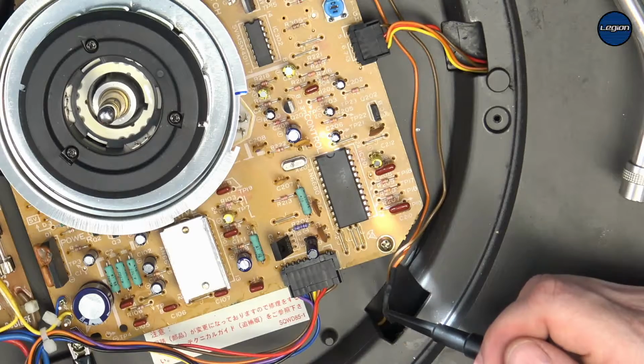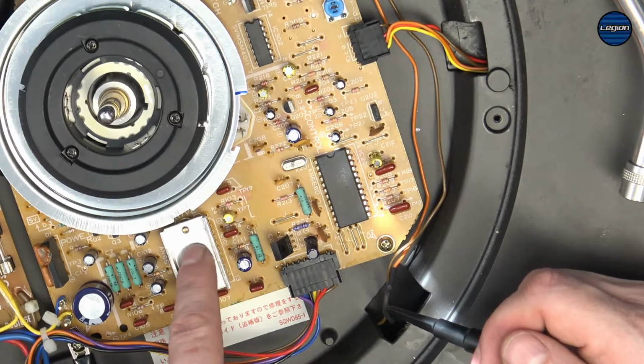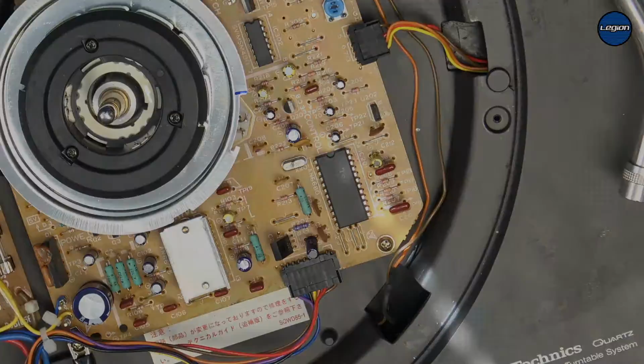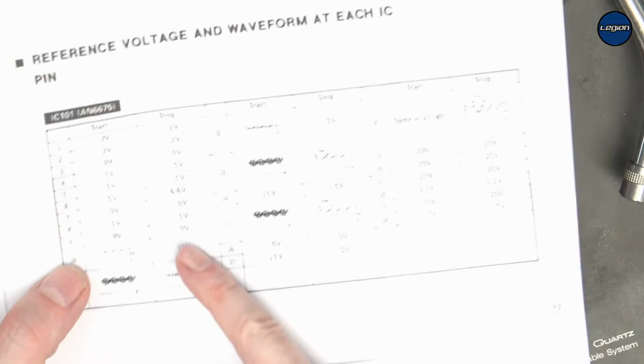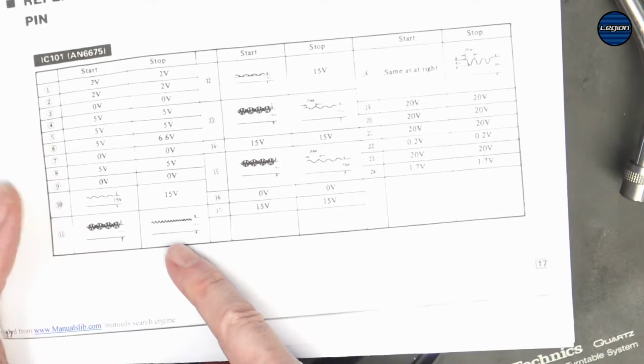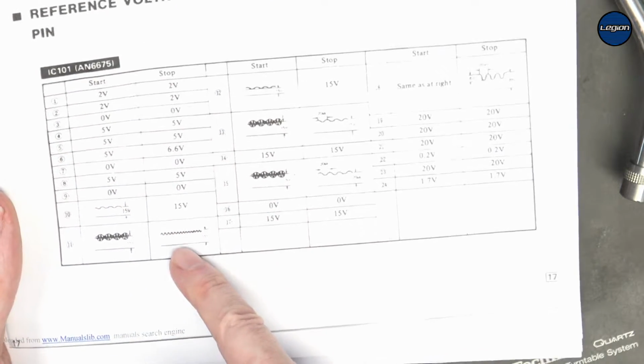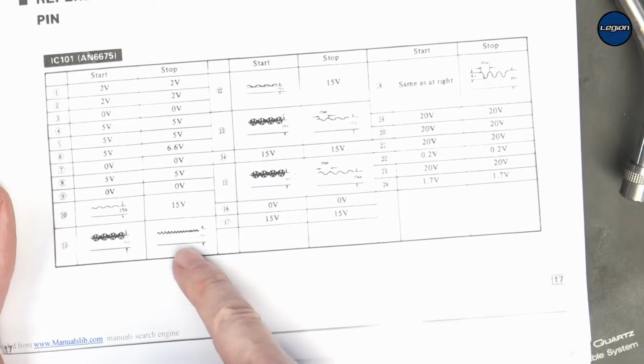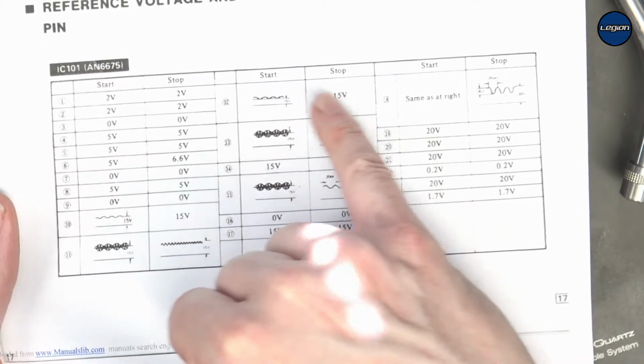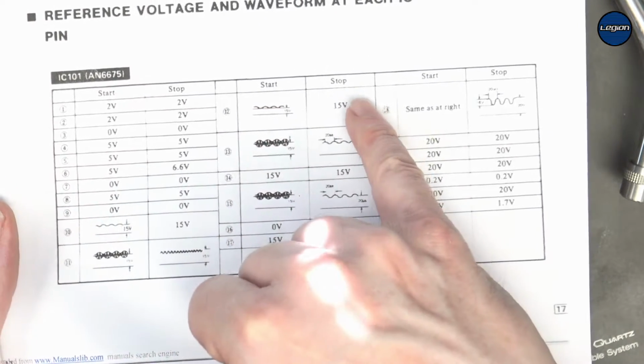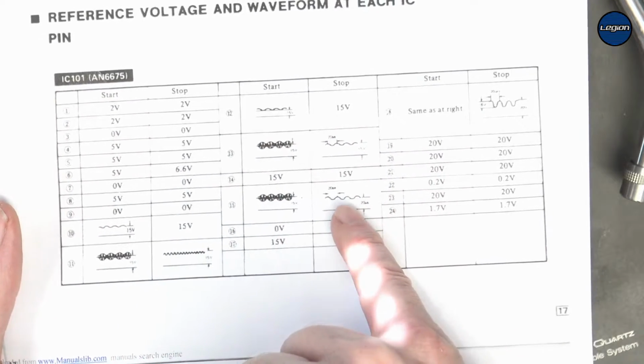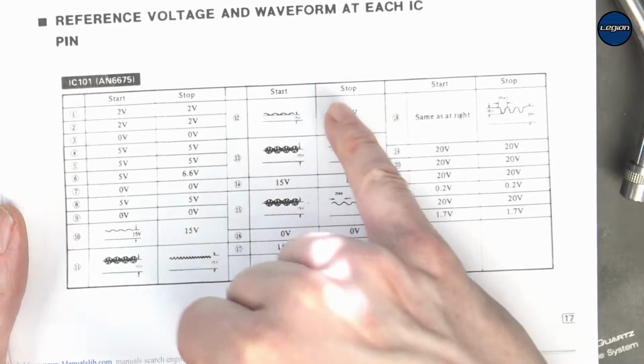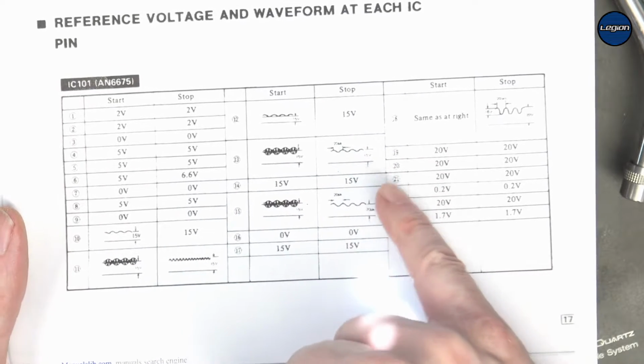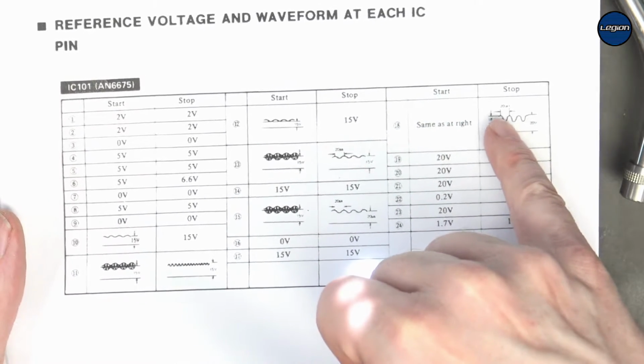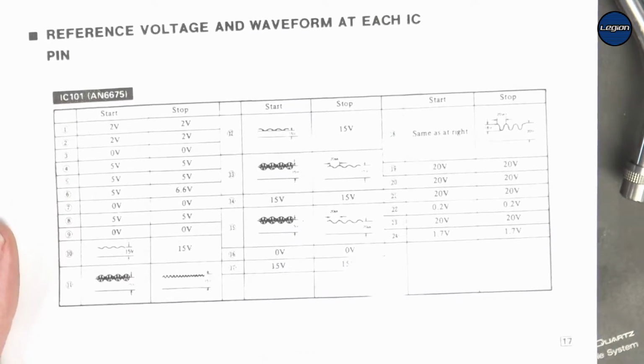So what I want to do next is check the motor control chip, this one, and look at what's happening on that. Okay, so looking at our service manual, IC 101, and we're looking at the stop column. So we've got pin 11. We'll check these because they've got waveforms for on and off. So 11, 12, 13, 14, 15, and 18. And let's look at what's happening with those.